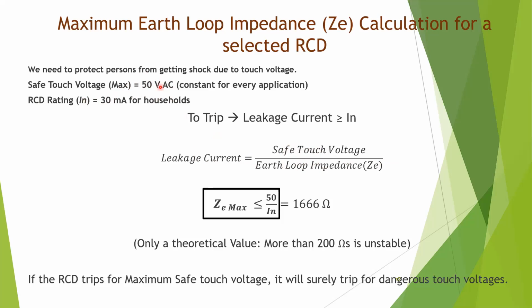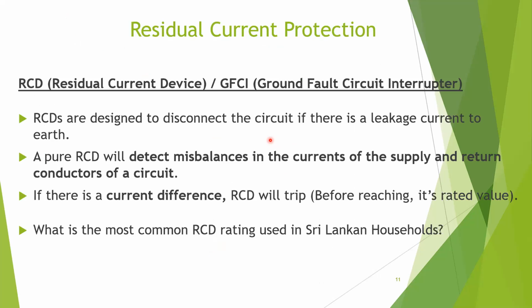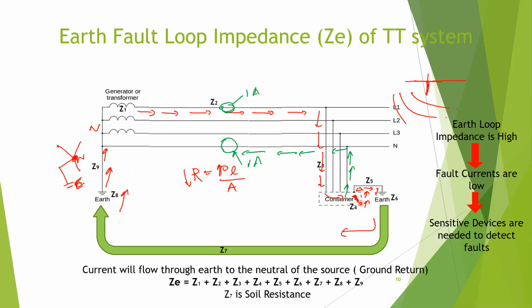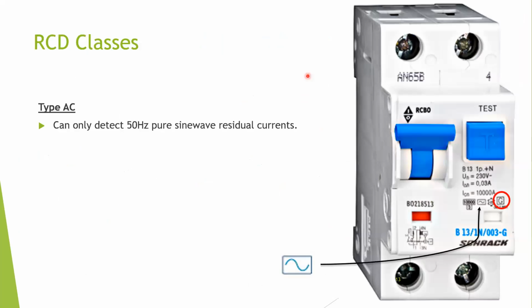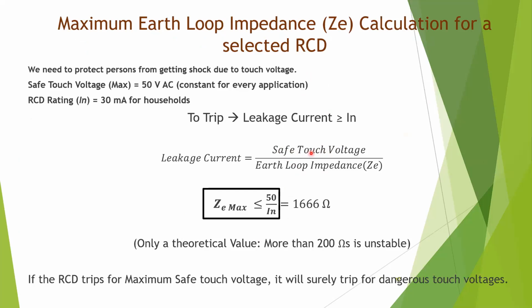You may wonder why we are using the safe touch voltage here. In this fault there can also be an impedance. You know that the live wire will be at 230 volts, but there will be an impedance in the fault, so there will be a voltage drop through it, and the enclosure might be at a different voltage because of that drop. Therefore we can't say the enclosure is at our rated voltage. That's why we take the safe touch voltage, because we need to protect people so that they will not get a dangerous shock.